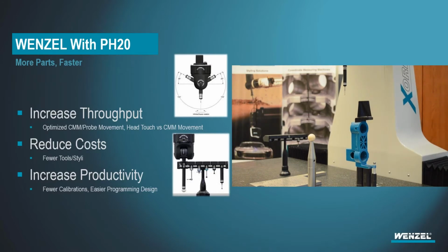So as you can see, that's about a 2.5-3 minute video. And we've gone through a wide range of angles, wide range of features very, very quickly, much faster than we would take with a traditional 3+2 CMM measurement. And what is the most important part is that entire CMM program that we just watched there was set up with one calibration. Due to the nature of the PH20 head, we can spend 15-20 minutes calibrating it, and then every angle that is selectable within the system is set as calibrated.